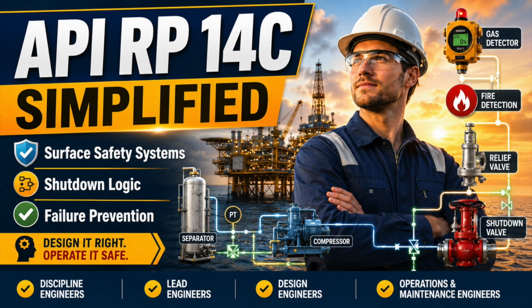Fail-safe behavior must also be defined physically. Loss of utility should move each final element toward the safest achievable state. That does not mean every valve closes. Some valves must open for depressurization. Some systems must remain running for cooling, firewater, or emergency power. The safest position depends on the scenario.